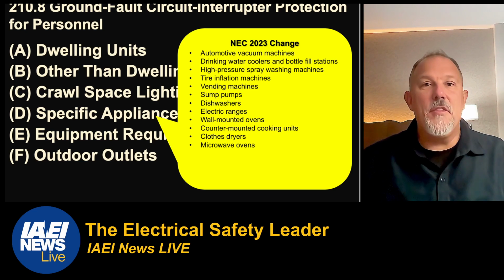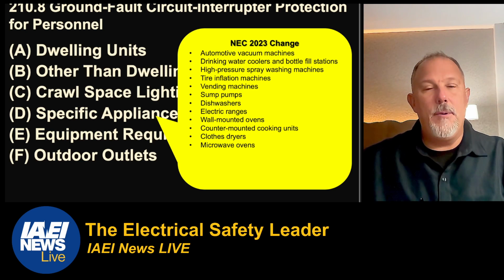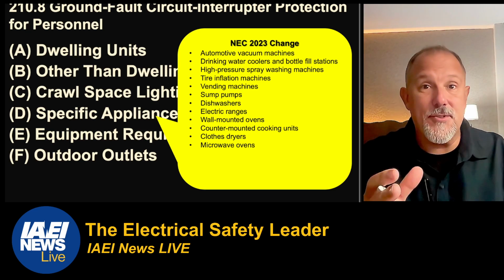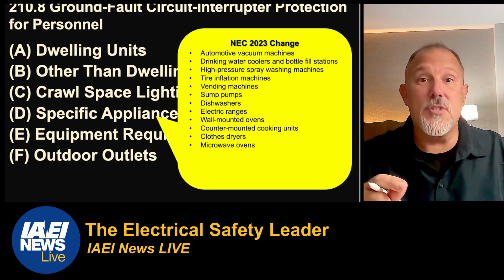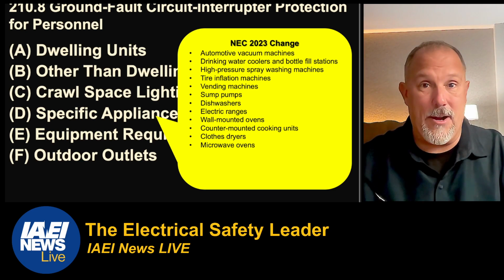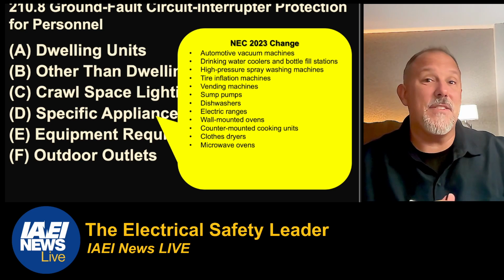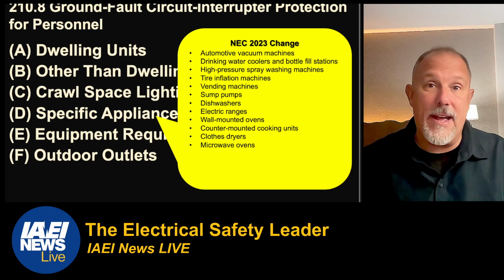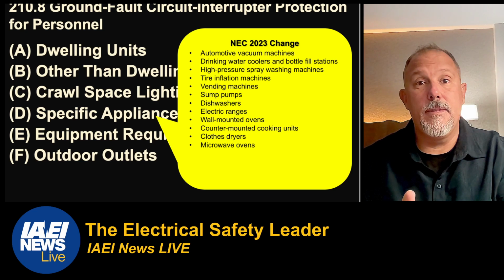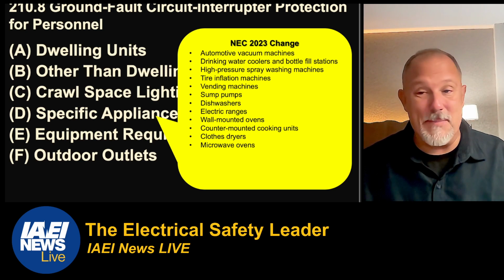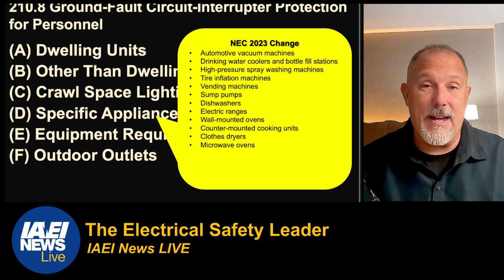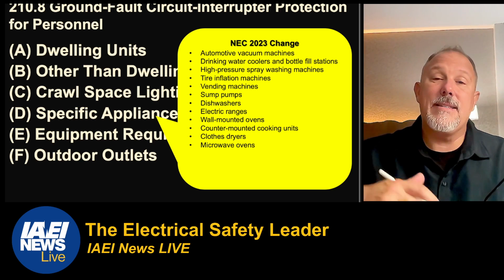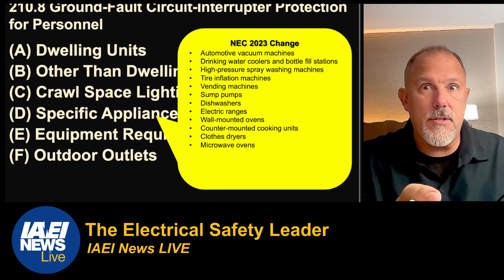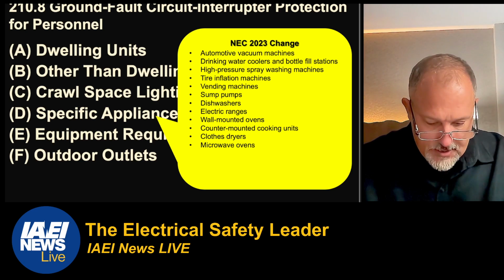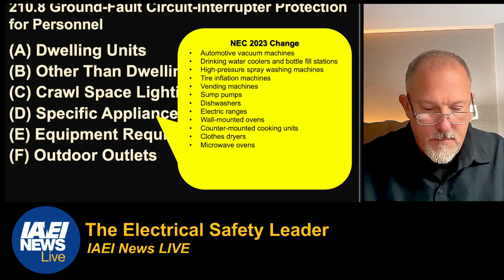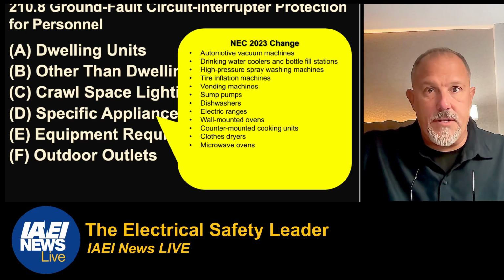But what about hardwiring? The hazard is not removed because you took the receptacle out of the picture. The hazard is not the receptacle. The hazard is what's plugged into the receptacle. And if I hardwire an appliance to get out of the GFCI requirements, you haven't removed the hazard. The hazard is the appliance. And I know if I was an appliance manufacturer out there, I'd say, well, you can't call my product a hazard. But any product at its end of life, or if I'm going to do maintenance on it, think about the requirements. Where is it? We have equipment likely to be serviced.